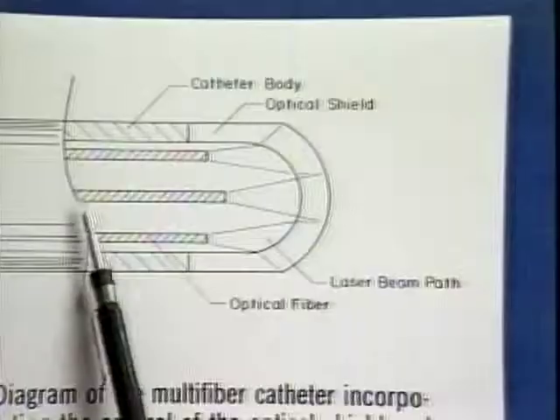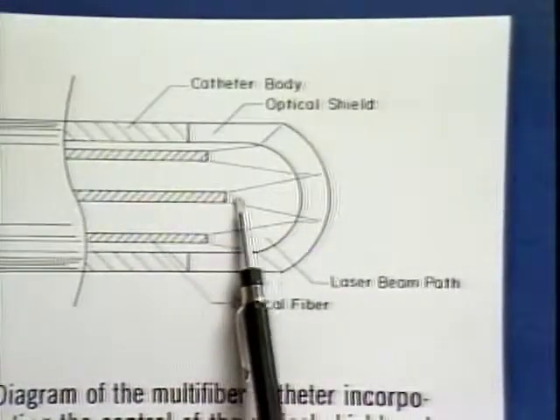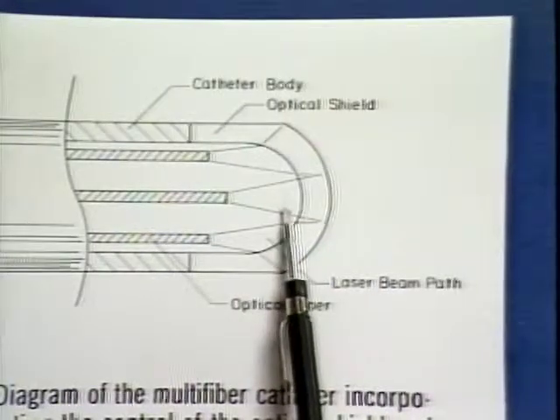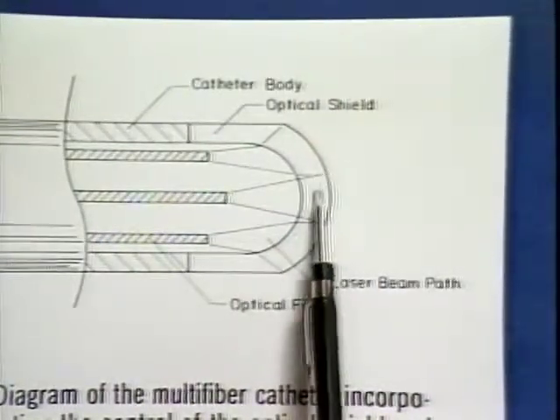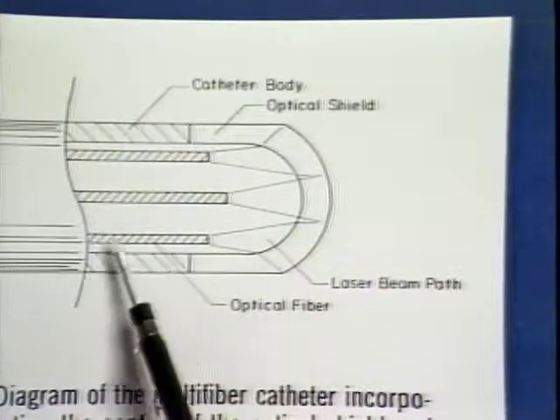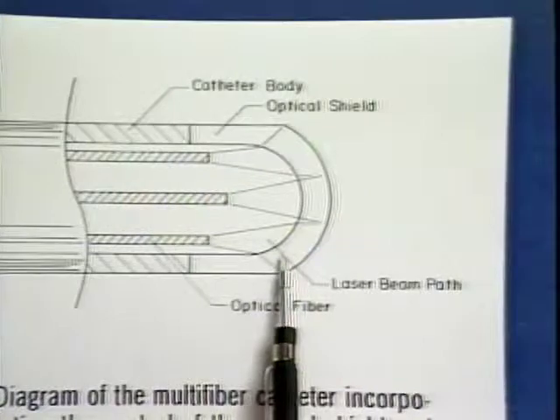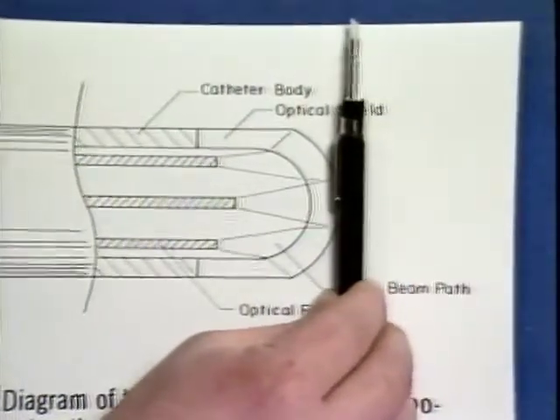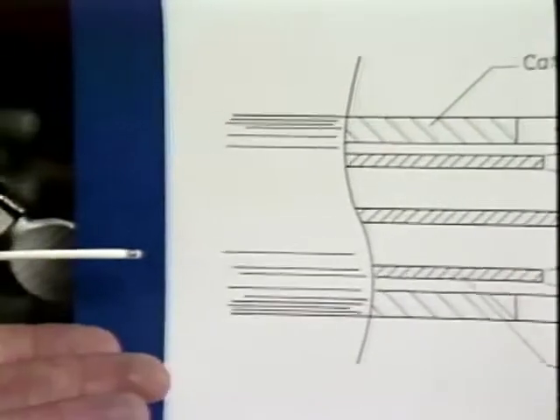This diagram illustrates that the optical fibers are placed at a predetermined distance from the output surface of the shield. By knowing this distance and the angle at which the light diverges from the fiber, we can determine the spot size on the output surface of the shield. Each fiber is aimed at a different location on the shield so that there is full shield overlap. The shield is then placed in contact with tissue. We set the laser power and exposure time by computer. With the spot diameter, laser power, and exposure time, we can deliver our photon dose and remove a very precise amount of tissue.